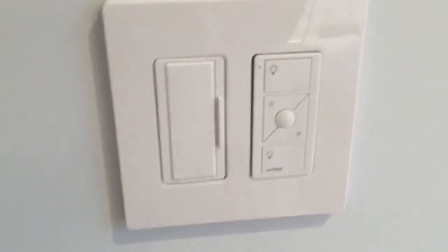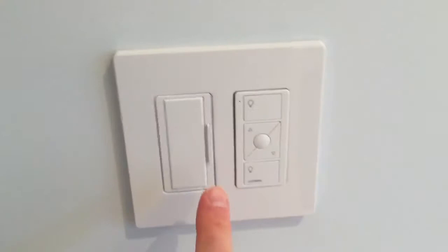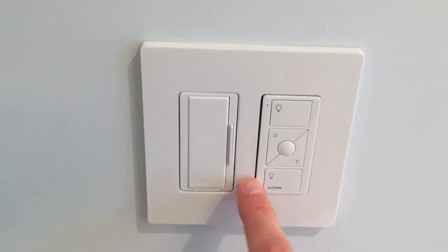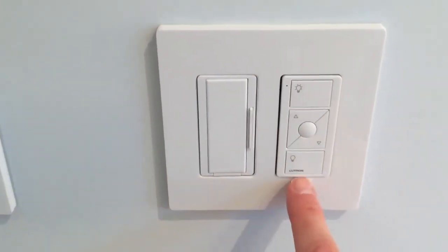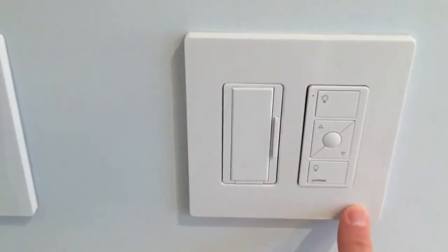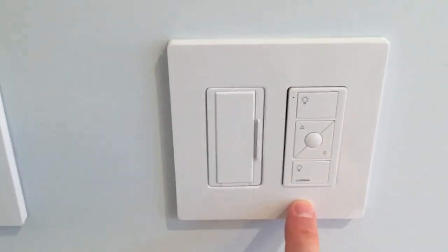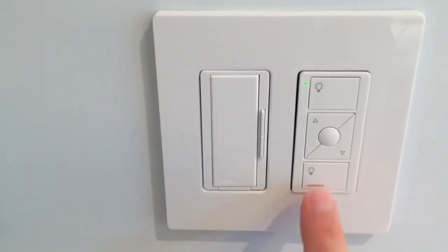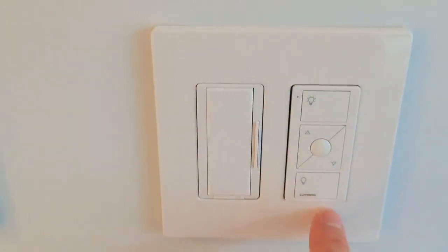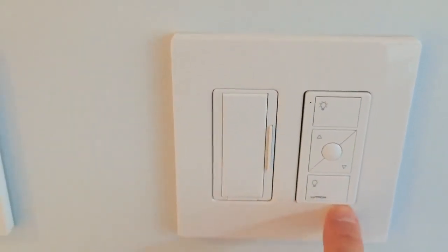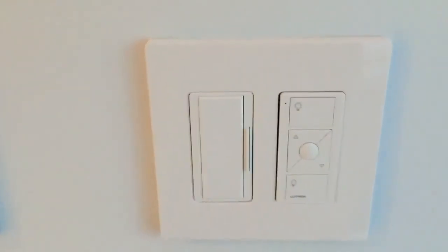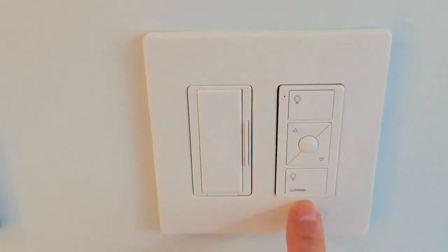The Pico controller can be placed on the wall. This is actually a single gang box with a 2-gang plate, and the Pico controller here is essentially double stick taped to the wall. There's no box behind here, but this gives us an inexpensive option for a keypad in this room. The nice thing about this is that if this system ever changes where we want to take out this particular keypad, we remove this, replace it with a single gang wall plate, and you'll never know that the Pico controller was there. There are also options for occupancy sensors.